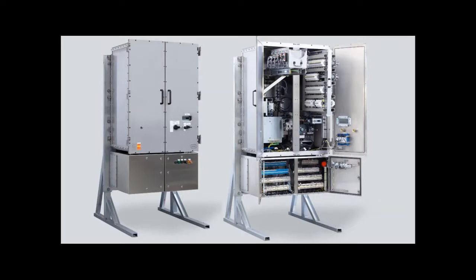If you can go to the left top side, Michael, this is the pull out rack of the automation system of the hydraulic. But this pull out system we have developed together to save place inside the enclosure. Left middle part is the controller of the automation, and in the left bottom side you can see star delta motor controller or motor starters for 2 motors of each 270 kVA for driving the crane. The right top is more or less a distribution board and interconnection for the valve control. And in the right bottom you can see the main switches.